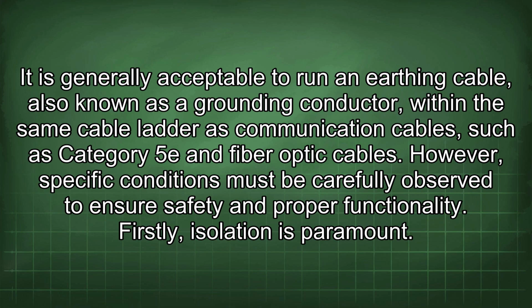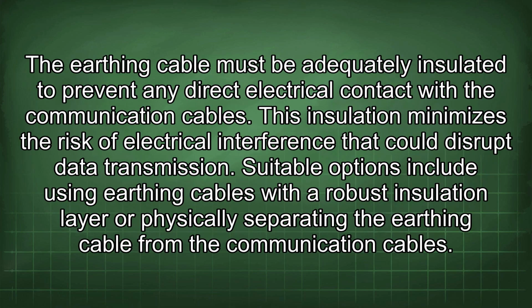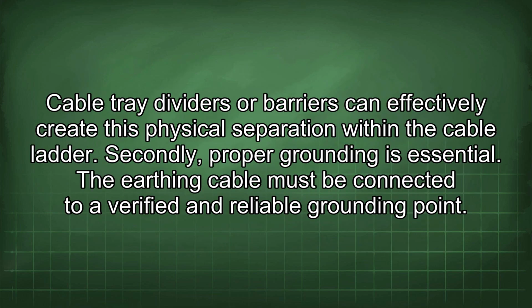Firstly, isolation is paramount. The earthing cable must be adequately insulated to prevent any direct electrical contact with the communication cables. This insulation minimizes the risk of electrical interference that could disrupt data transmission. Suitable options include using earthing cables with a robust insulation layer or physically separating the earthing cable from the communication cables. Cable tray dividers or barriers can effectively create this physical separation within the cable ladder.